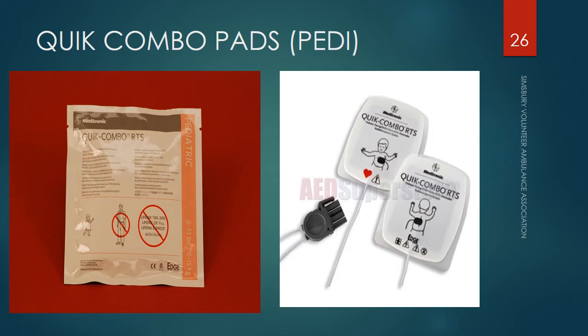The reason why the pads are a little bit different for pediatric patients is because when we put them on the LIFEPAK 15, which is the cardiac monitor that the paramedic carries, we can dial in the number of joules we want, whereas the AED only gives a certain amount of joules. And the pediatric pads that are made for the LIFEPAK 500 have a pediatric attenuator on them. And again, just make sure, because there have been a few times at Simsbury Volunteer Ambulance where I've opened up the LIFEPAK 500 and found the QUIK-COMBO pads for a pediatric patient that are specific to our LIFEPAK 15 sitting in the AED pocket, and you don't want the wrong AED pads there.